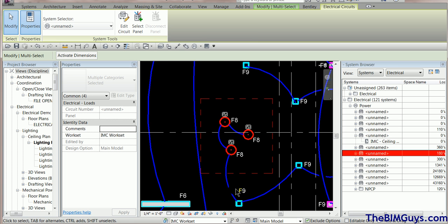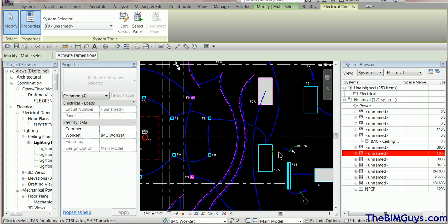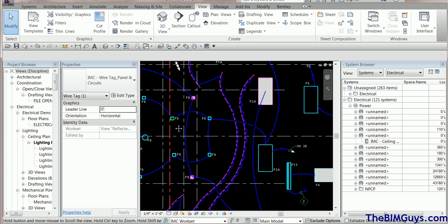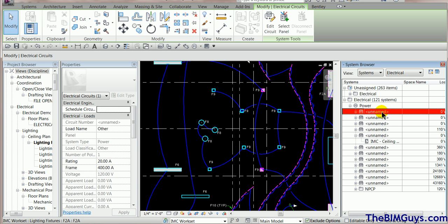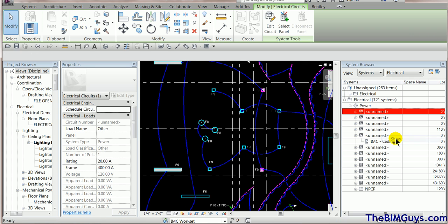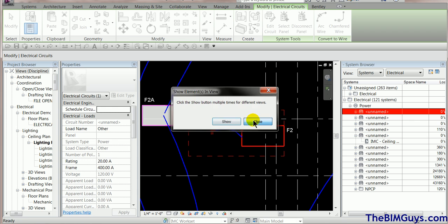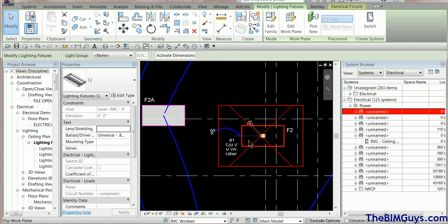If I grab those fixtures and look at the Electrical Circuits properties, it says 'unnamed' — they don't have a panel yet. So if you run a home run off these, you may have a problem. As you go through and find these little oddities, select them in the System Browser, right-click, and choose Show — it'll take you right to those unnamed fixtures.